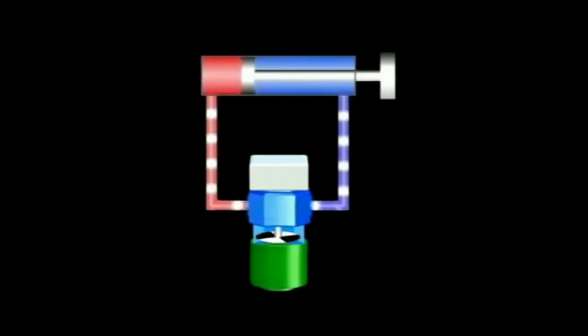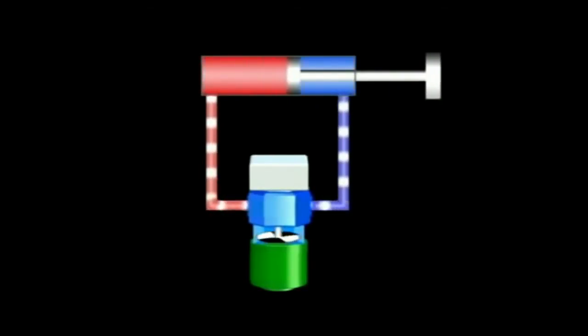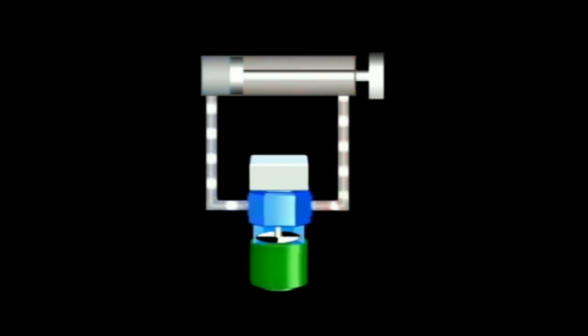In addition, pressure and flow volume control valves are not used, so there is no energy loss from control valves. Compared to earlier servo valves, energy consumption has been cut to just one tenth.